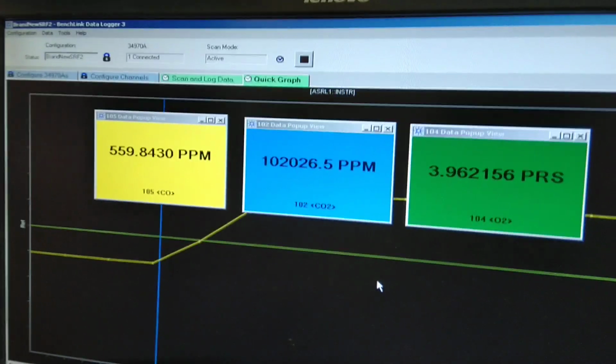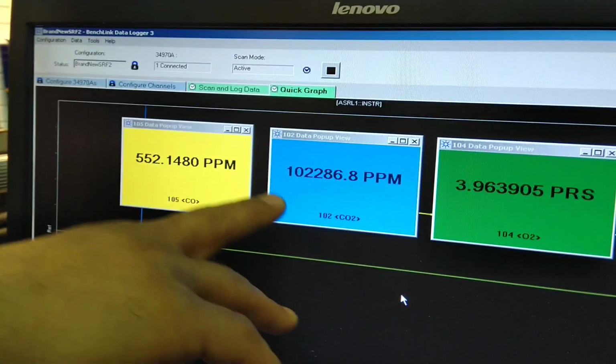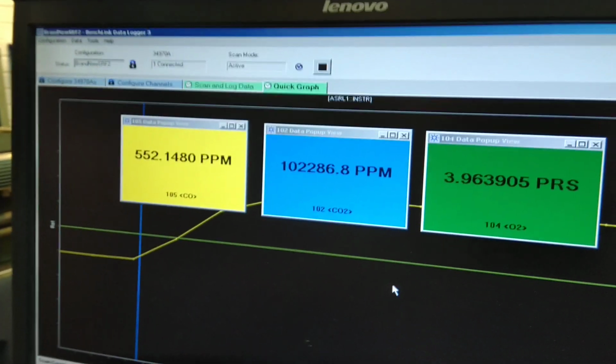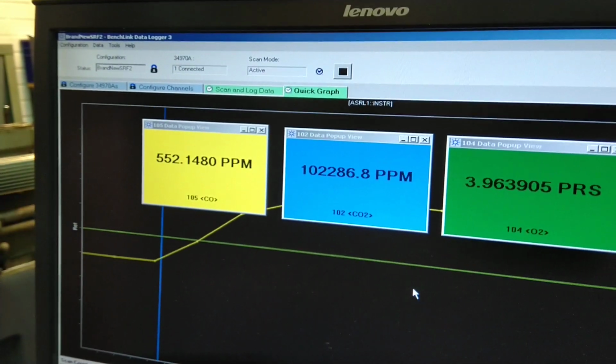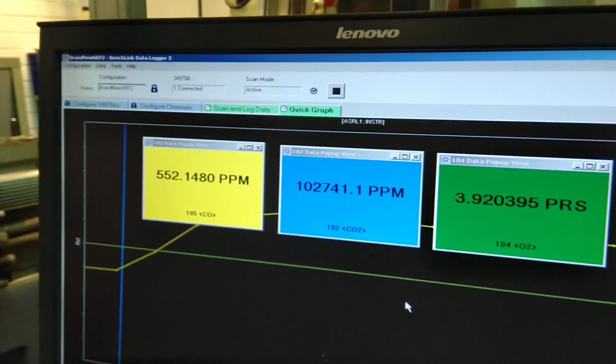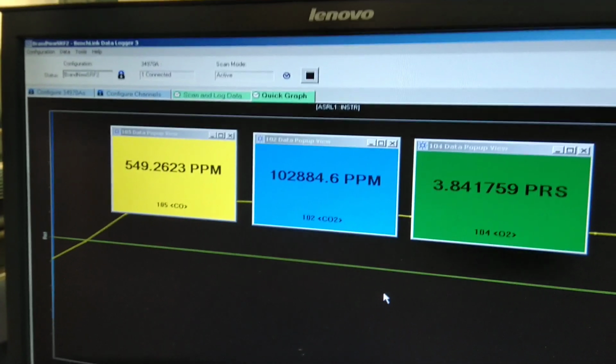excess oxygen in the flue gases, and now you have this around 10% CO2 on dry basis, similar to the other analyzer, and around 500 ppm.